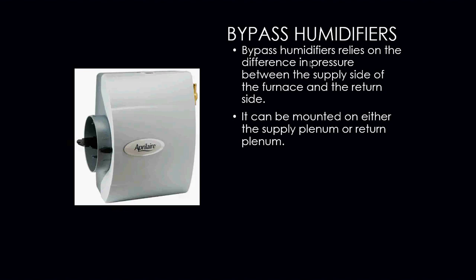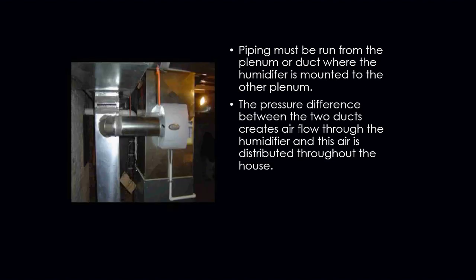These types of humidifiers can be mounted either on the supply or on the return. When it comes to humidifier location, it is recommended to follow the manufacturer's recommendation of where to locate it. There are many different mechanics out there who will tell you different things, but the best way and the best place to install that humidifier is by following those manufacturer's recommendations.